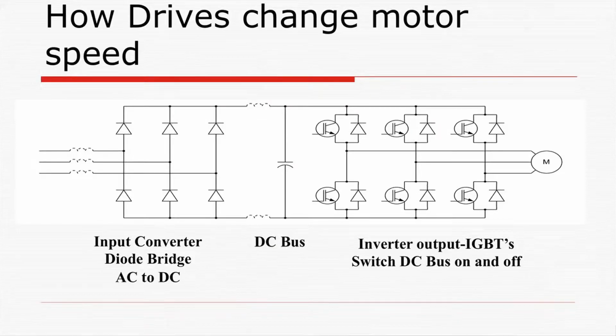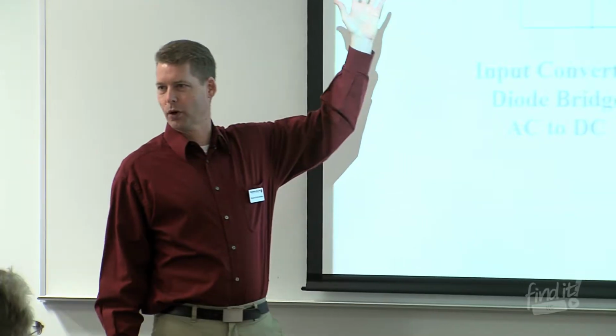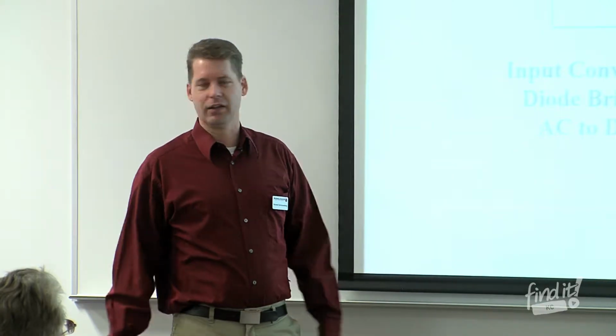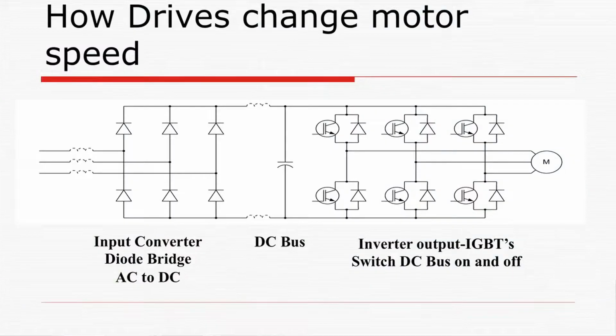So internally, electrically, what's inside the guts of a VFD? This is an electrical diagram of any VFD that's out there on the market now, a standard six-pulse VFD. There are 3 sections to a modern VFD. You've got the input bridge, the diode bridge converter section of the drive. You've got a DC bus or energy storage portion of the drive. And then you've got the output section, the IGBTs or inverter section of the drive. That's where the transistors inside the drive, the magic of the drive, turn power on and off and send it out to the motor.